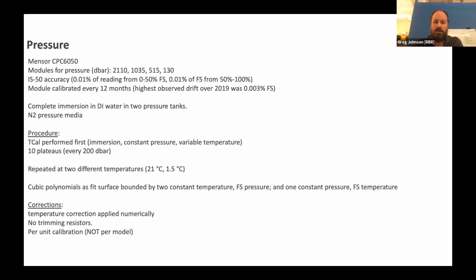One, it means that the temperature variation in the tanks is fairly low for kind of adiabatic effects. And secondly, it means that we can do it quite quickly and also do a leak test at the same time. So we do that temperature calibration first, which is the immersion across constant pressure but variable temperature. And then we do 10 plateaus divided over the full scale. This example's from a 2000 dbar sensor. And 21 room temperature and cold, and then the cubic polynomials.